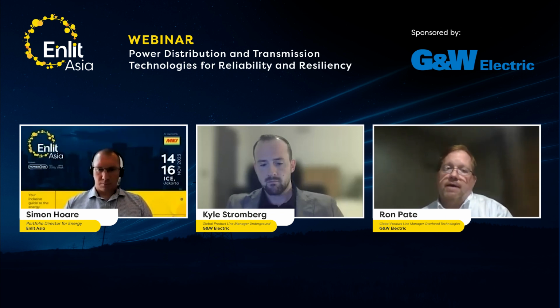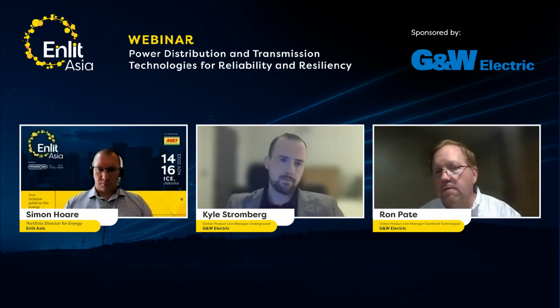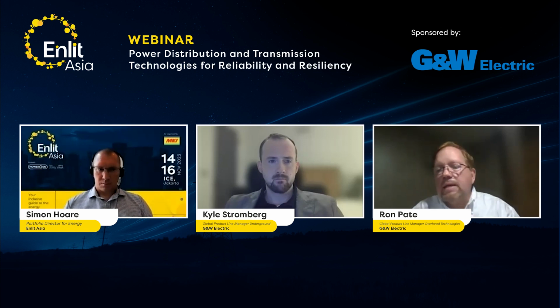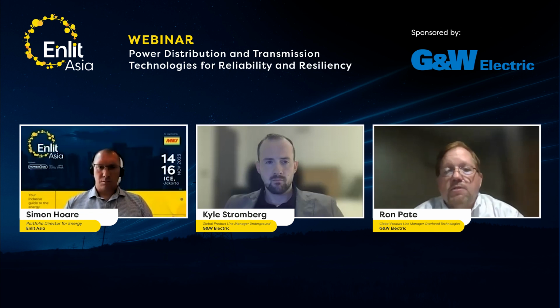As you start to have these renewables employed, you also have to look at the type of fault currents they can create. Renewables like solar cannot create the same level of fault currents as spinning generation, but they can change the fault current characteristics in the local vicinity. So you need to carefully monitor what's actually happening where you interconnect to these renewables. That's an area we've been specializing in for quite some time with reclosers, AccuSense sensing technologies, and so forth.